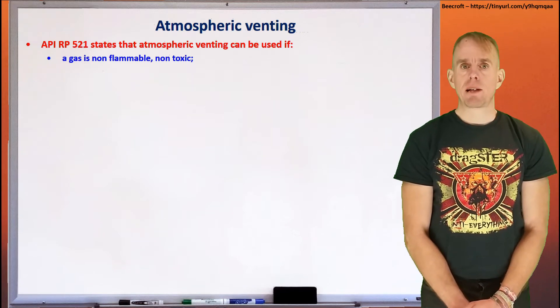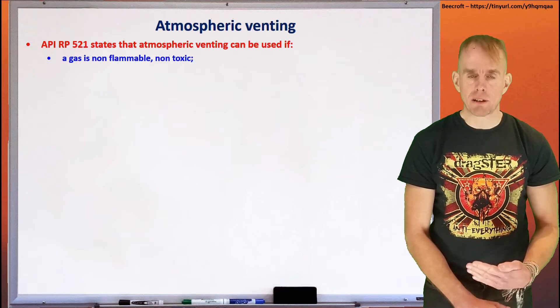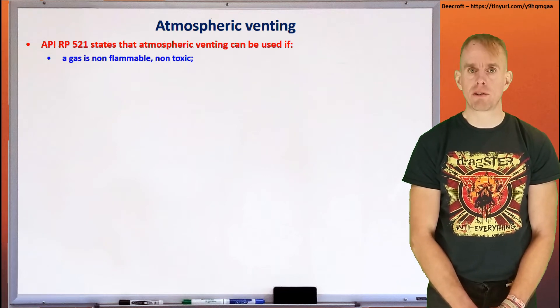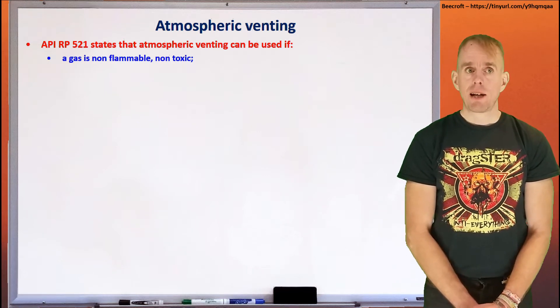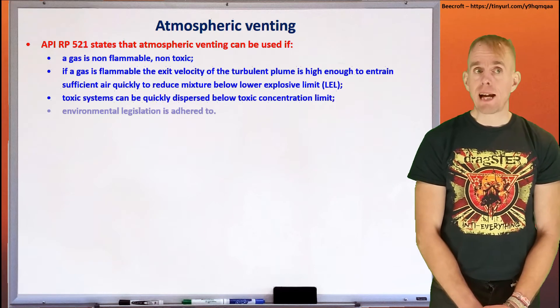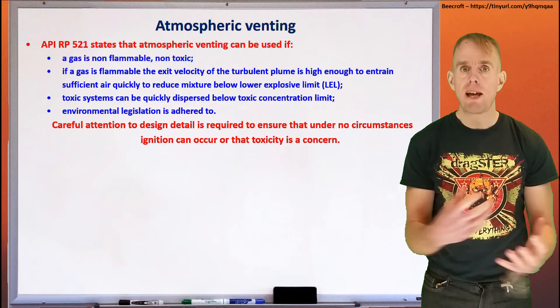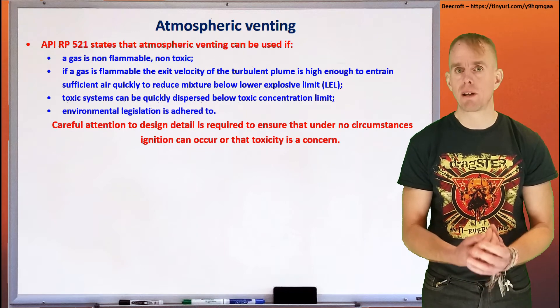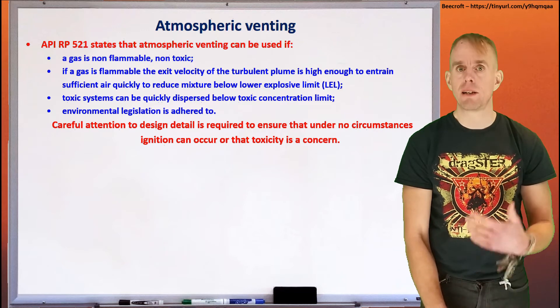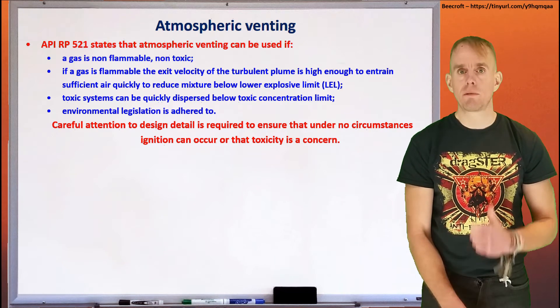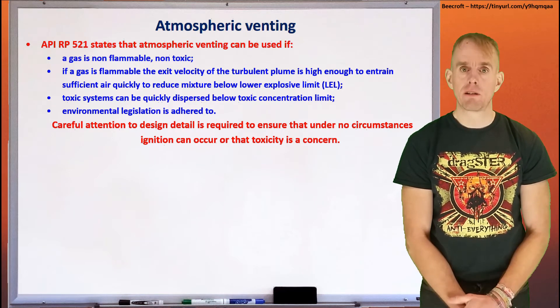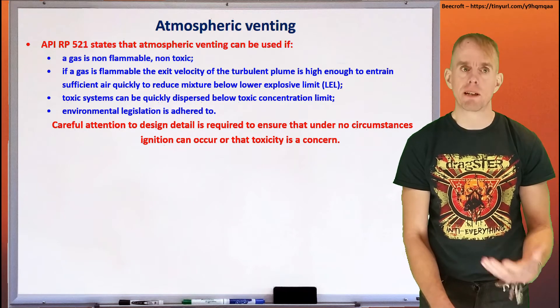So let's think about atmospheric venting. There are various pieces of established guidance in this area. The American Petroleum Institute RP521 is one of those established pieces of guidance, and this states that atmospheric venting can be used if a gas is non-flammable, non-toxic — if a gas is flammable and you can entrain enough air into it quickly enough to reduce the mixture below the lower explosive limit. With toxic systems, if you can quickly disperse the gas below any toxic concentration limit. But at all times, environmental legislation has to be adhered to. So it may not be possible in the toxic case to sufficiently disperse, in which case you're going into scrubbing and treatment systems.